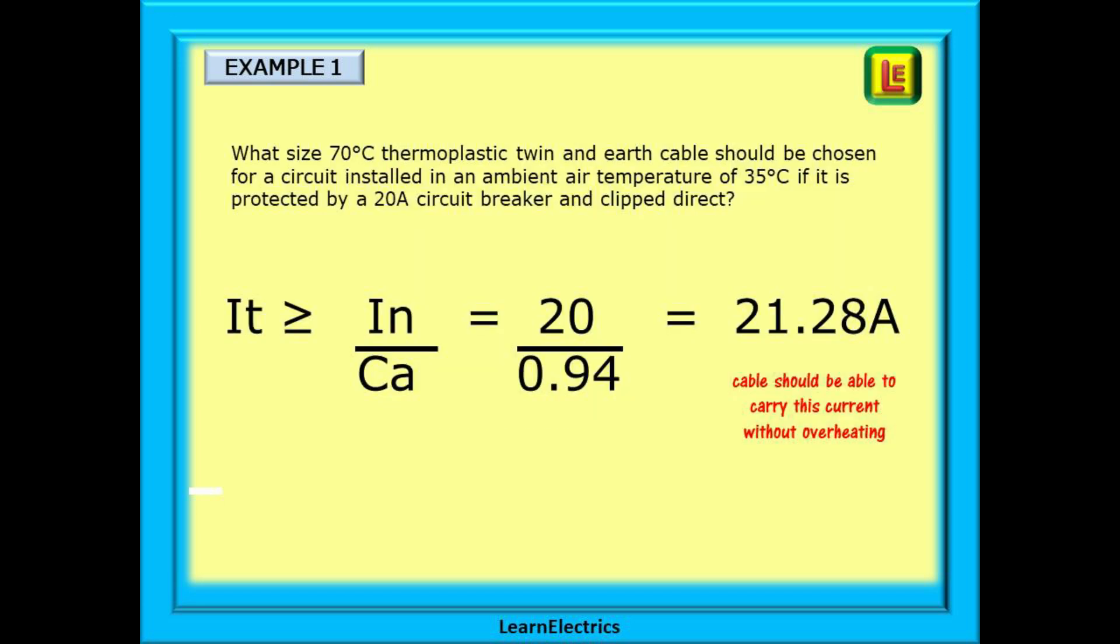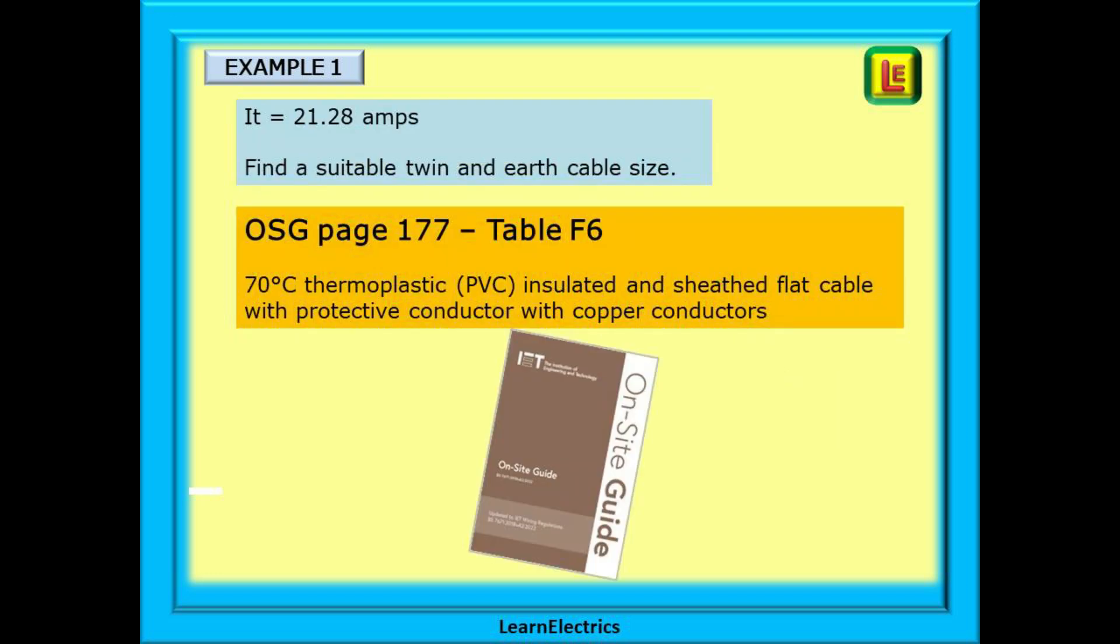So follow this through. 20 divided by 0.94 is 21.28 amps. The cable we choose should be able to carry this 21.28 amps of current and chosen correctly, it will not overheat under these conditions. So we now know that IT is 21.28 amps and we must find a suitable size cable.